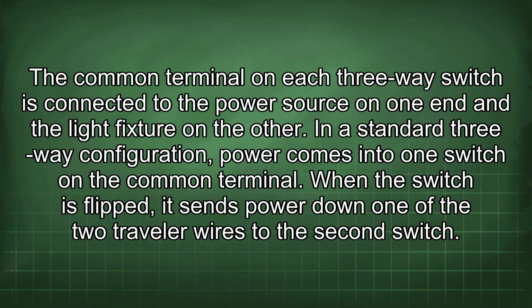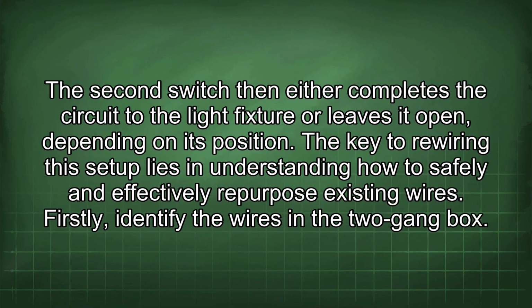The common terminal on each three-way switch is connected to the power source on one end and the light fixture on the other. In a standard three-way configuration, power comes into one switch on the common terminal. When the switch is flipped, it sends power down one of the two traveler wires to the second switch. The second switch then either completes the circuit to the light fixture or leaves it open, depending on its position. The key to rewiring this setup lies in understanding how to safely and effectively repurpose existing wires.